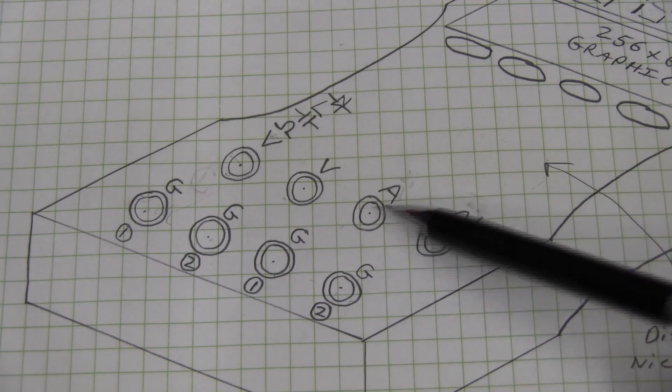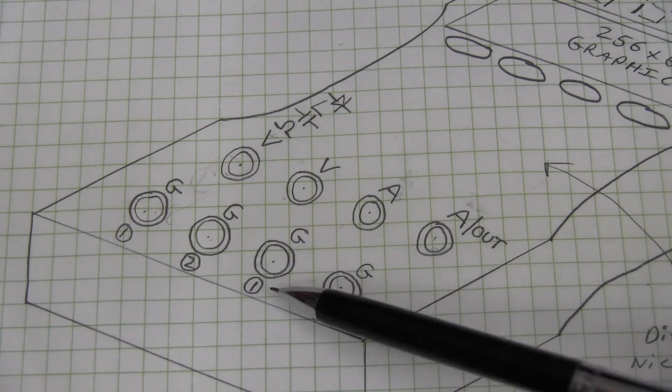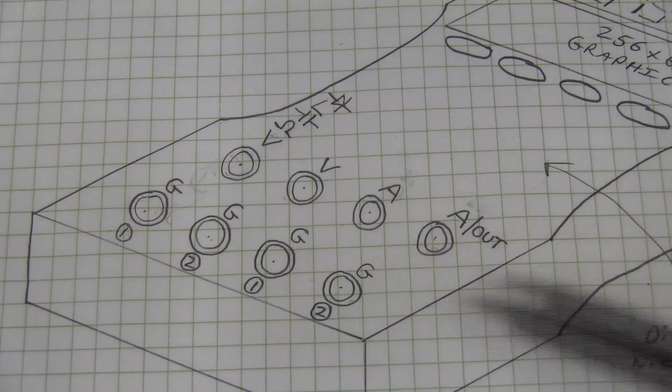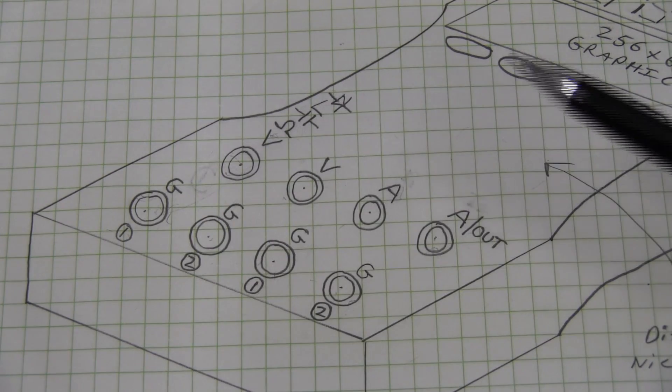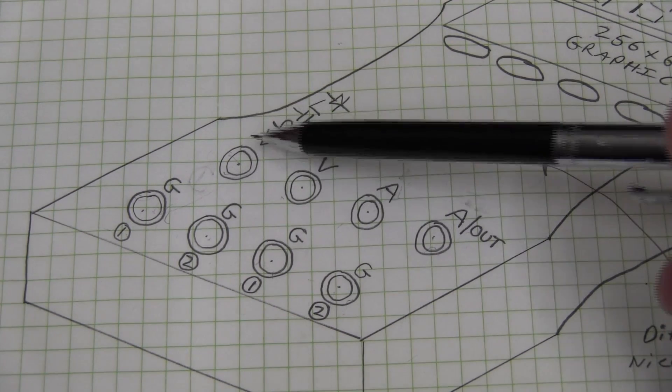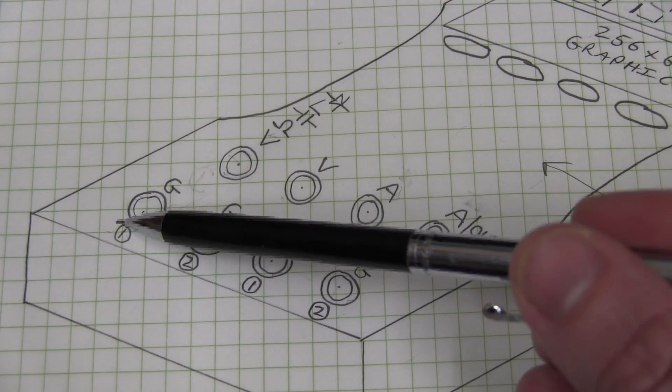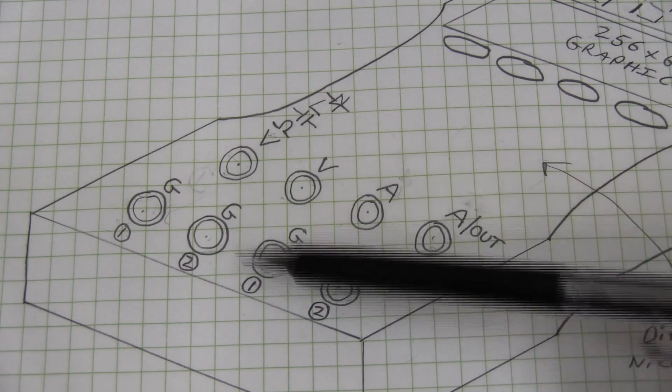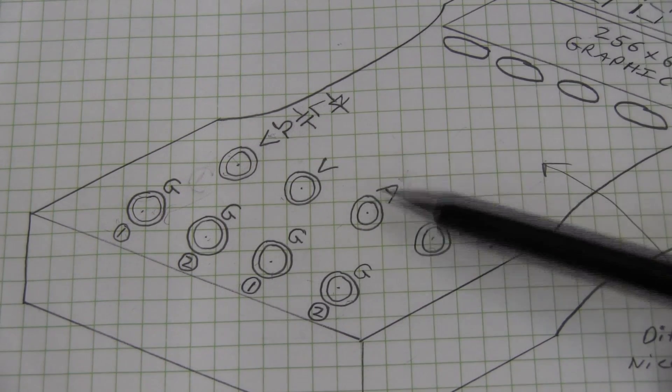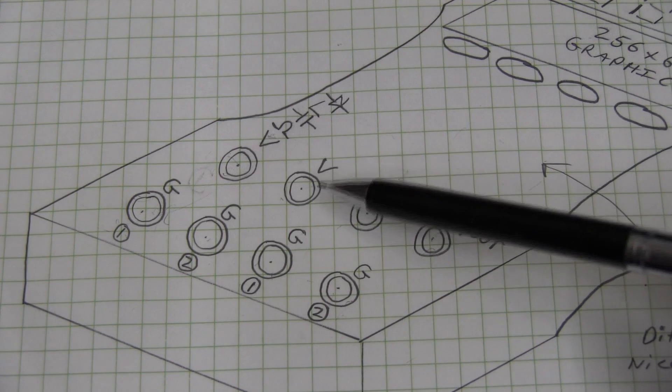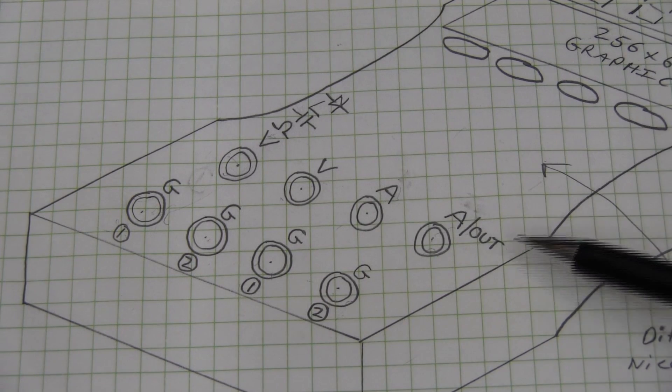So you can combine just like on the Gossen energy multimeter, you can combine volts and amps. That's why I've labeled them channel one here. You can take, say, if you're talking power, you can take channel one volts times amps and it can display power. Likewise, on the second channel, volts and amps displays power.